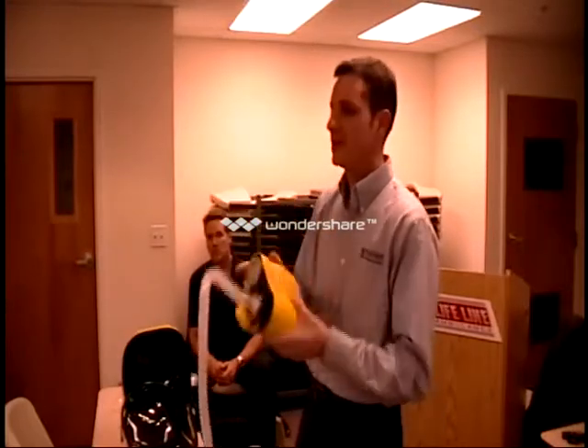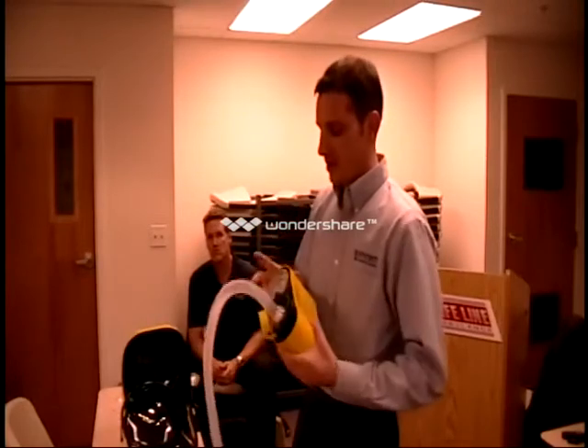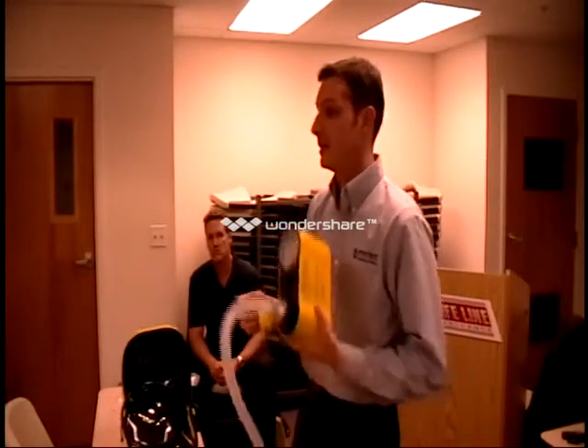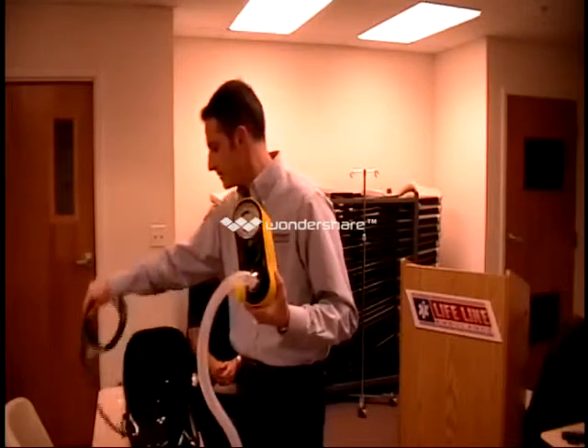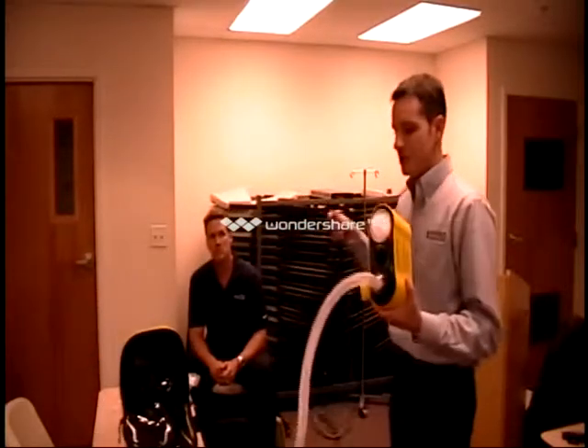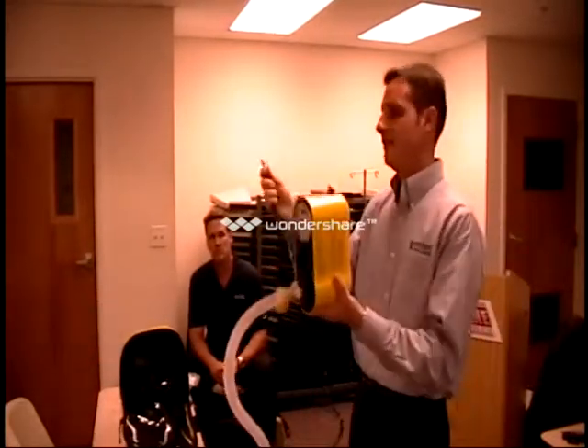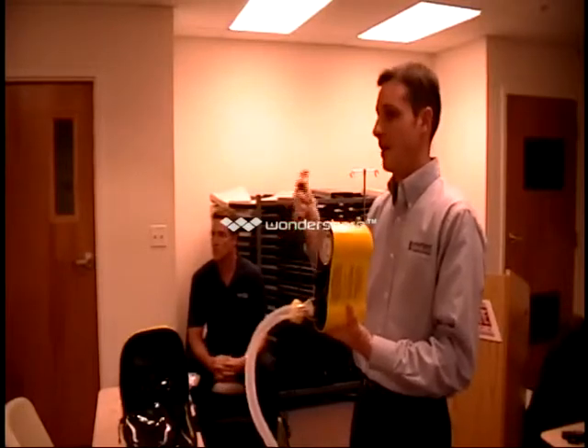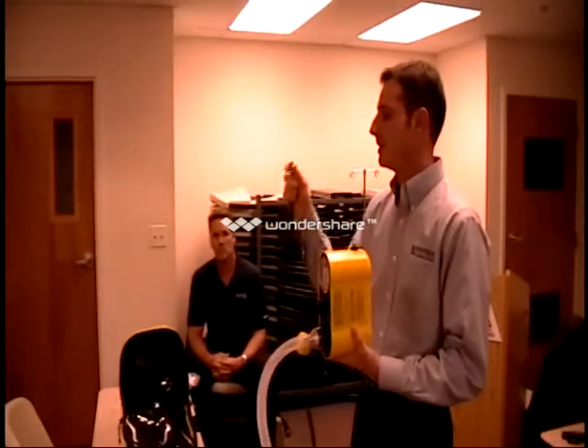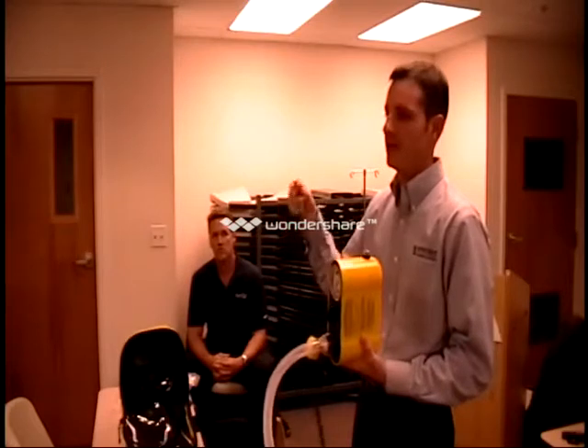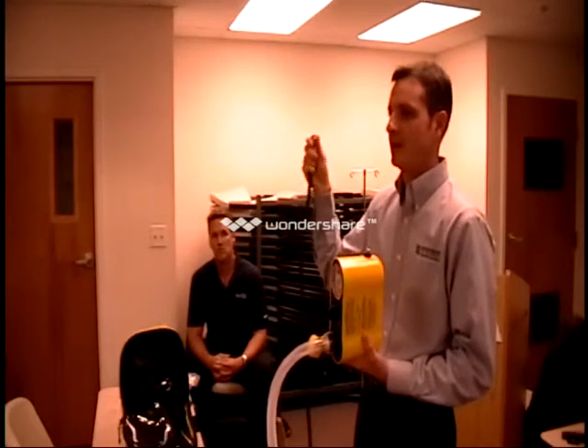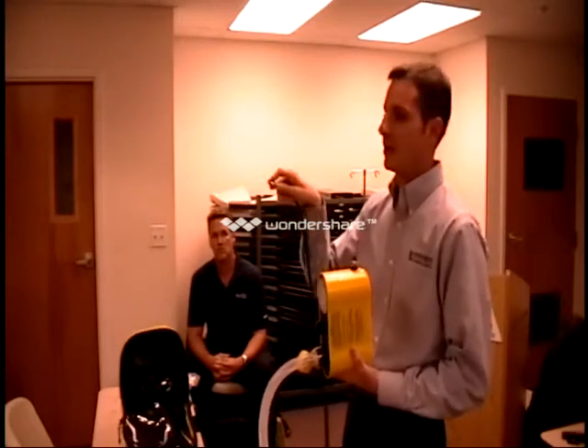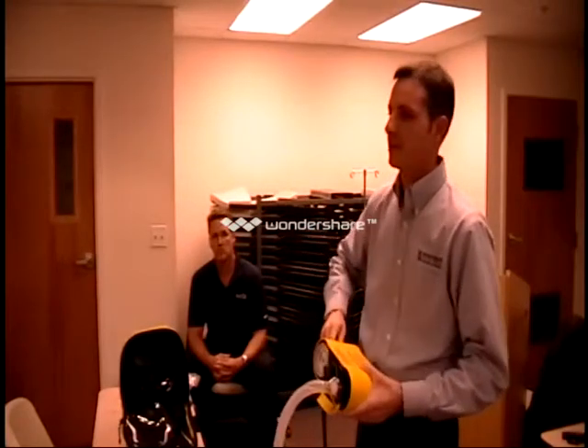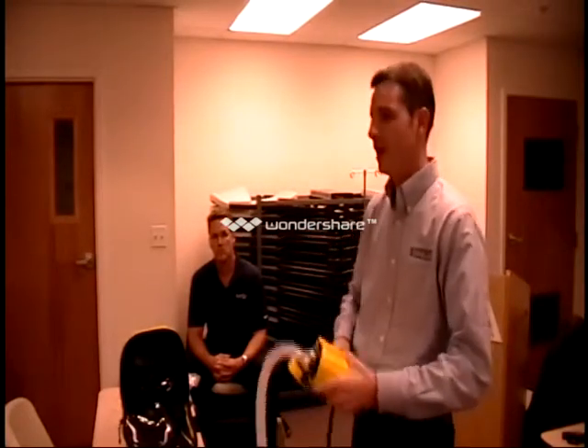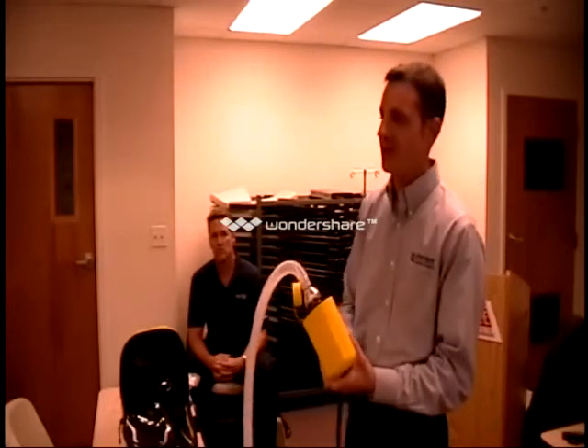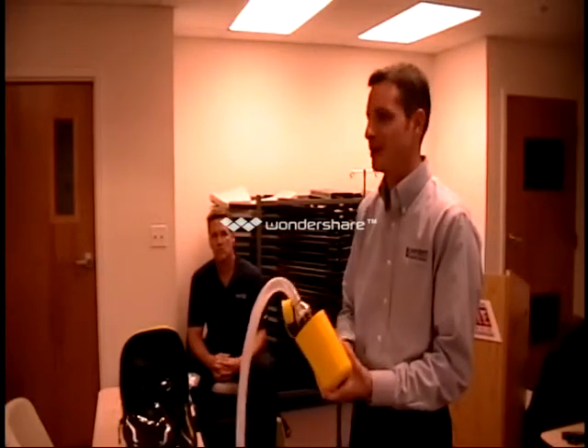There's only a couple things on this device. Your high pressure inlet, your manometer, and your CPAP regulator here. That's it. On your high pressure inlet, since you're using high pressure, you do not need Teflon tape, and you do not need a wrench to tighten this. Everything's thumb tightened. This is a loose hex nut here, so once I turn on the cylinder, the pressure will actually create the seal. So if you use a wrench, you're going to end up over-torquing it, probably breaking the washer off in here. So just remember, everything's thumb tightened on here. If you have trouble unscrewing this, make sure you turn the cylinder off first, drop the pressure, and then you can unscrew it.